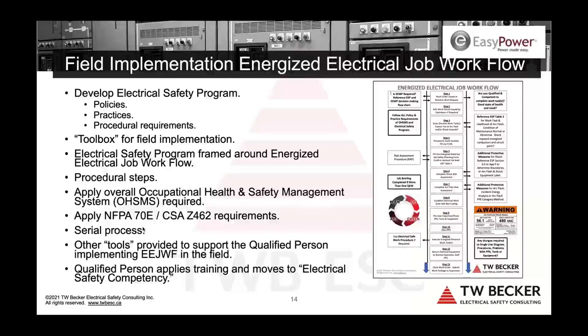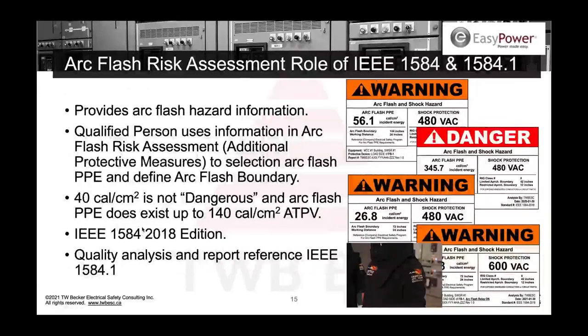So the arc flash risk assessment and the role of 1584 and 1584.1. Again, it's arc flash hazard information for the qualified person when they're executing that energized electrical job workflow in the field. This is the best method to give them this information. We also have the arc flash PPE category method. If there's no calculations completed, that can also be used. And we could apply a label with the arc flash PPE category number on it and the arc flash boundary and working distance from the arc flash PPE category tables.